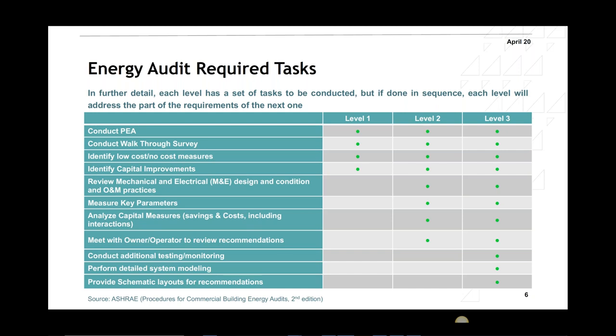Level three, you'd need to conduct additional testing and monitoring, staying more on site, doing more measurements for a longer period of time. The longer the period, the more accurate the results would be. A detailed system modeling. Normally, people use the energy model, as you would do the energy model. We're going to talk about that later as well. And you need to provide schematic layouts for the recommendation. So it's not just an idea saying, you know, change this into that or change this pump. You need to show some kind of schematic on how this should be done, with a little bit of specifications as well.